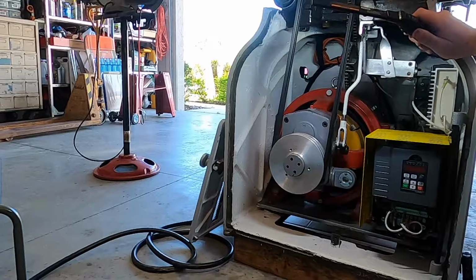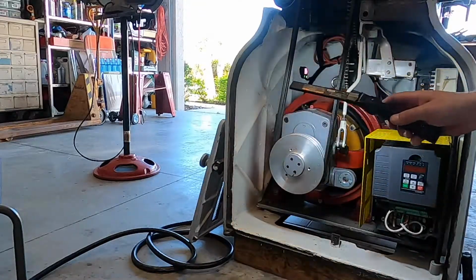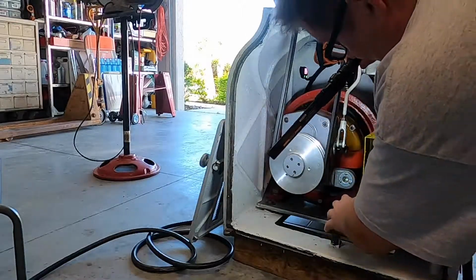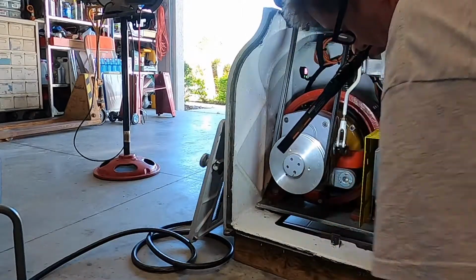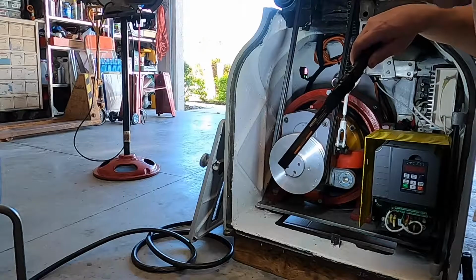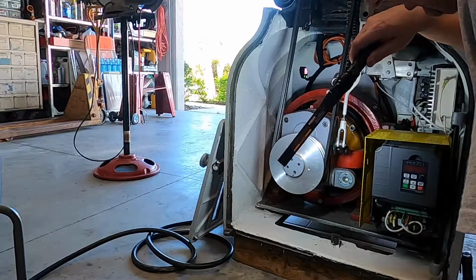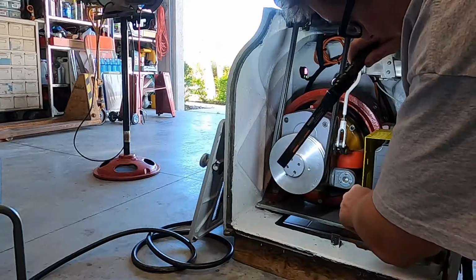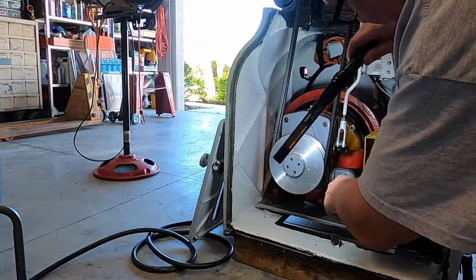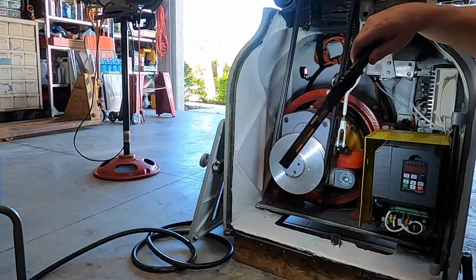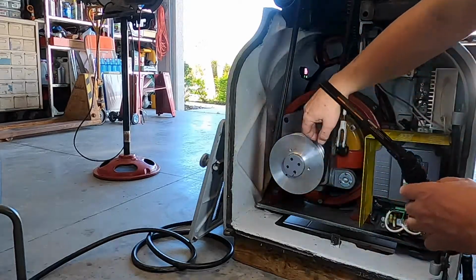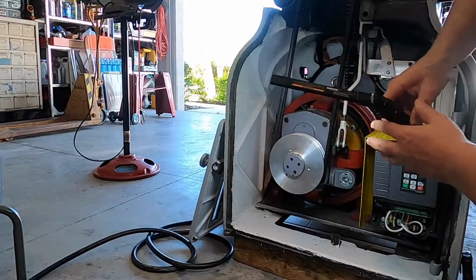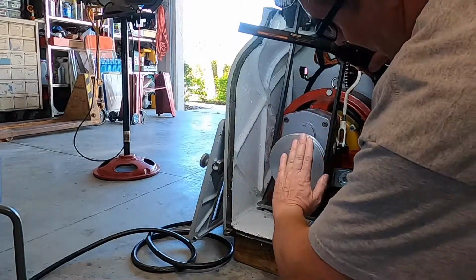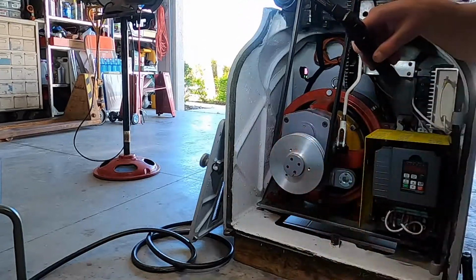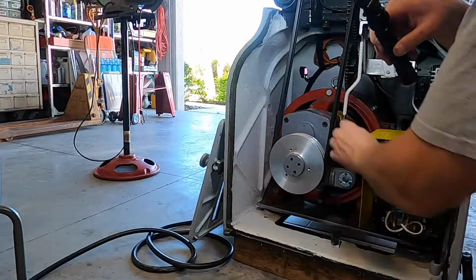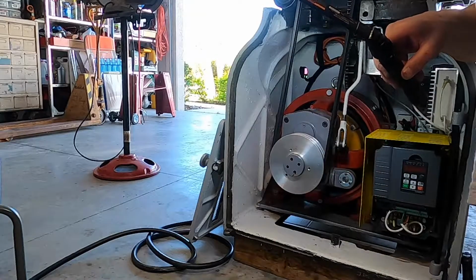Putting the whole Reliance case back into the frame here requires shimming it. Shimming it was dead easy - I had 6 shims, so I started with 1 shim each on the front and 2 shims each on the back, and it was perfect the first time. By perfect, I mean I had perfect alignment in these pulleys top to bottom - the pulley here on the bottom wasn't canted in or out, it was straight up and down. That keeps the belts aligned nicely, so I'm really happy with that.